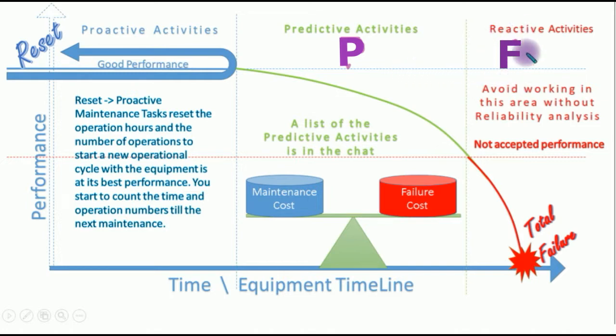Here, that's the failure — when you start to have some failure in the function. The function is not complete. For example, if you're having a pump and the pump is not delivering the quantity needed, so it's less than needed, then that's a potential or functional failure, a partial function failure. Or the pump is having some leakage — that's a partial function failure. Many other partial function failures start here. You detect that there is a failure in the equipment physically — you detect it with sound, with performance, with your ears, with your smell, and so on.